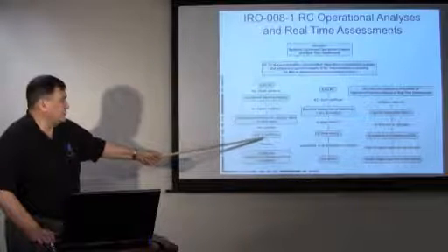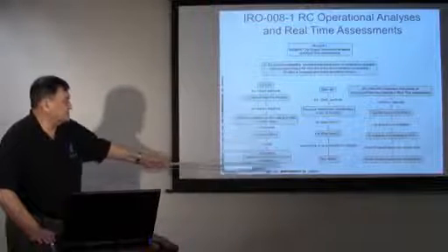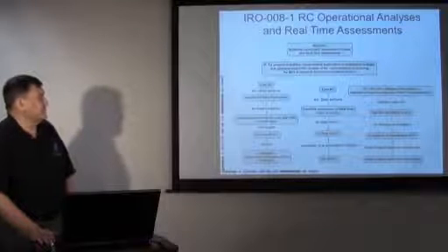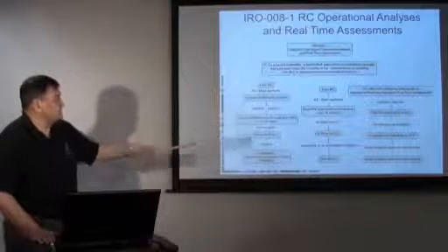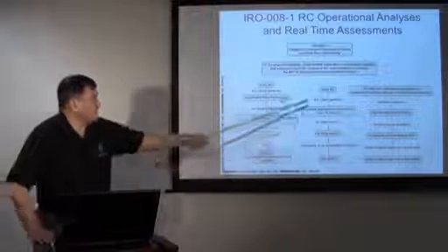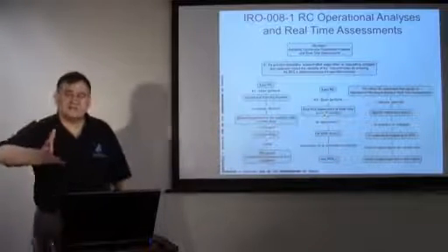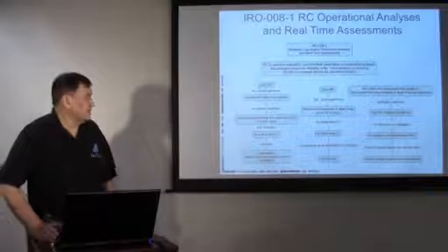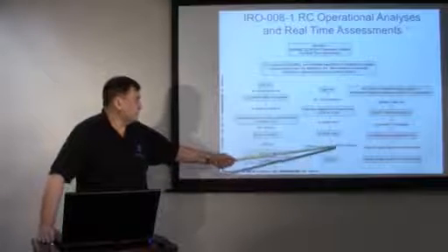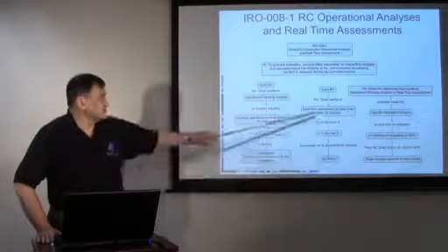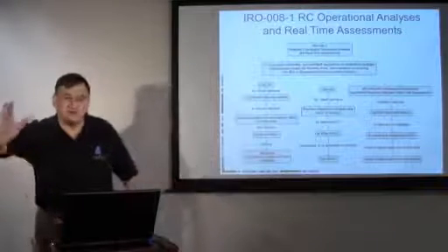and will exceed the IROLs during anticipated normal and contingency events. And this one is somewhat redundant with the earlier standard, but the main new one here is that they'll perform a real-time assessment at least once every 30 minutes of the wide area, and is it exceeding or expected to exceed the IROLs. And so this one really means you've got to run all those contingencies.